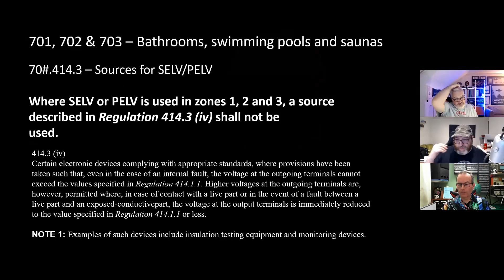And this is the little snapshot from 414.3.4, which just refers to electronics being used to achieve protection. It says certain electronic devices comply with appropriate standards where provisions have been taken such that even in the case of an internal fault, the voltage of the outcoming terminals cannot exceed the value specified in 414.1.1. That's just SELV and PELV.